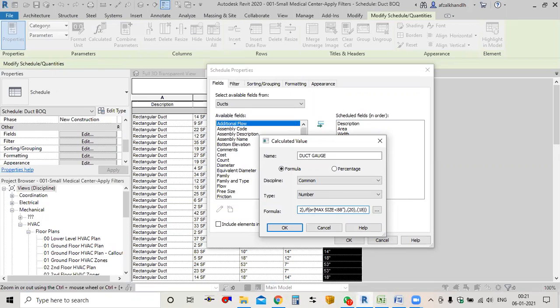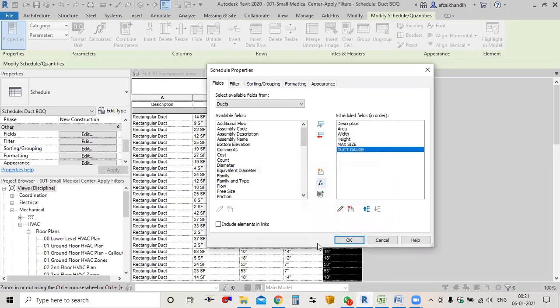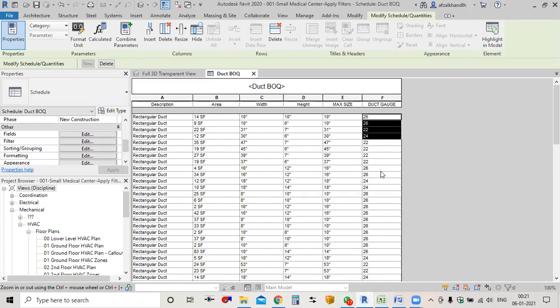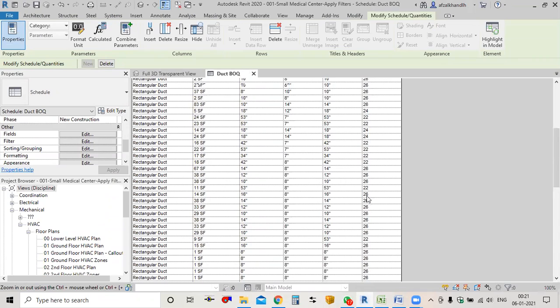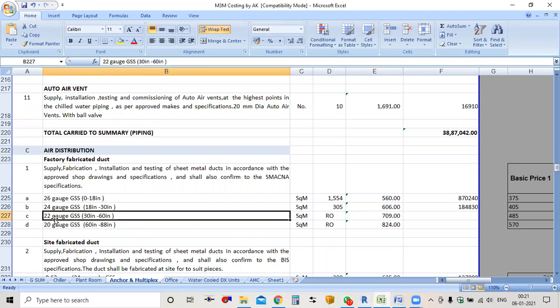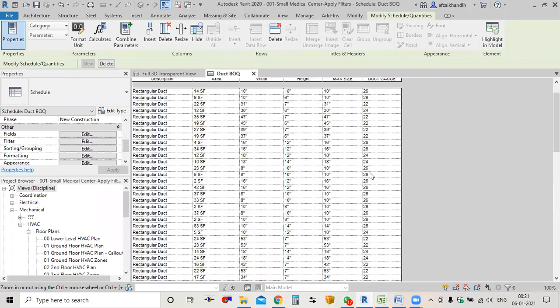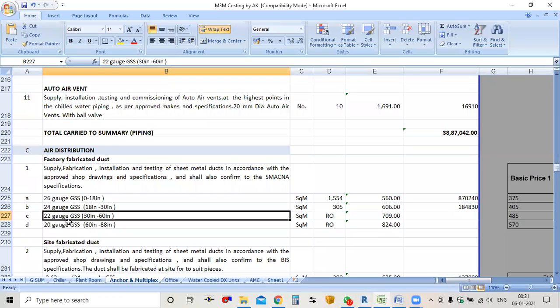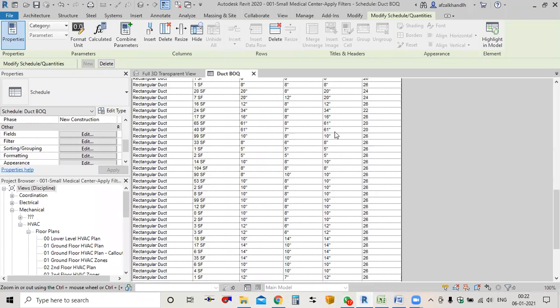Click OK. The parameter is now perfectly working. You can verify: a duct with maximum size 45 should lie in gauge 22 — and it does. Another duct with size 61 should lie in gauge 20 — and it shows 20 gauge. So it's working perfectly.